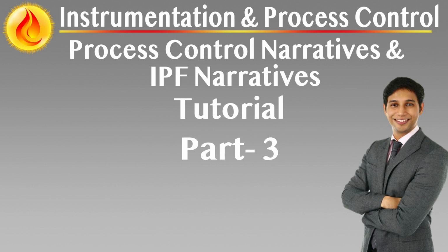Process safety time and response expectations. For each IPF, the process safety time, the maximum allowable time between hazard detection and achievement of the safe state, must be defined. Based on this, response time requirements are specified for logic solver execution, signal propagation, final element actuation, e.g. valve stroke time. These values are used to verify that the IPF meets performance targets and can intervene fast enough to prevent escalation of the hazard.